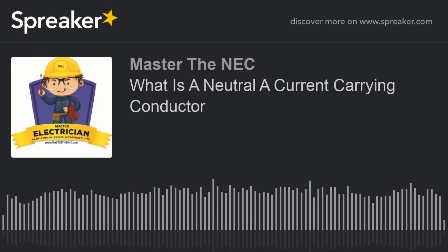Okay. Now, branch circuits and feeders is where we see it the most, and they supply these major nonlinear loads. Again, the current on that neutral can be as great as much as 2 times, okay, 2 times that of the current in the ungrounded conductors. Okay, it becomes cumulative or additive, and that is a serious problem.